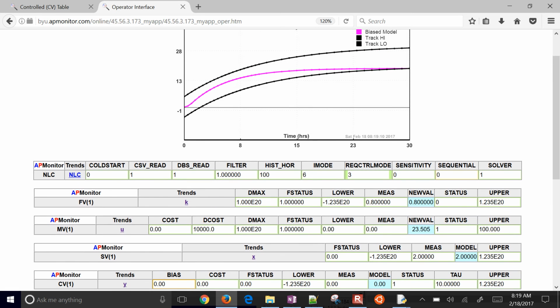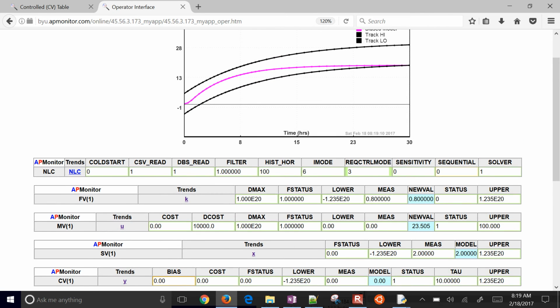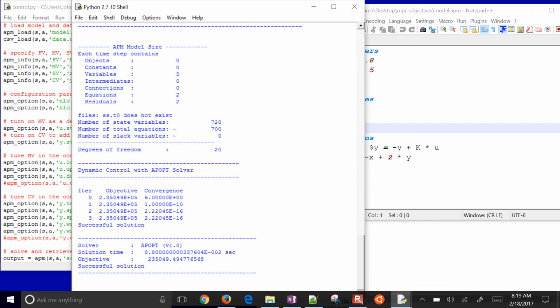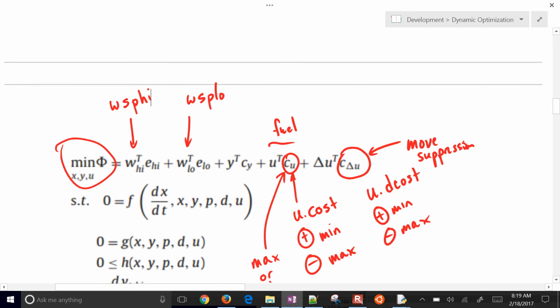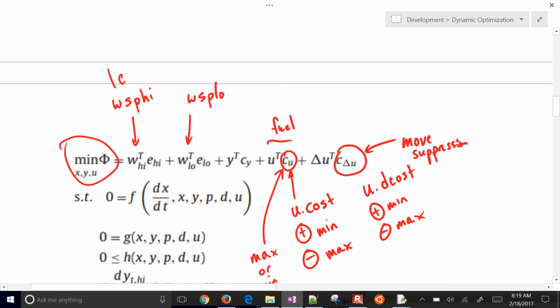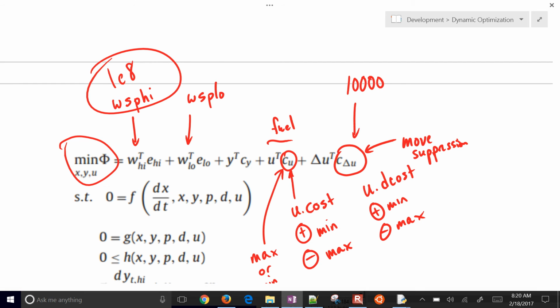It may still be, oh no, it worked well that time. So the weight set point high was able to overcome that very large DCOST value that I had right here, the penalty for the MV movement. Tuning is all about the relative amounts of these tuning values that you put in. It's all relative. If you have this one as a very large one, 1e to the 8th, and this one might be 1,000 or 10,000, then this one is going to win because it has a higher weight. So you have just one objective function and you're changing the values in that objective function.